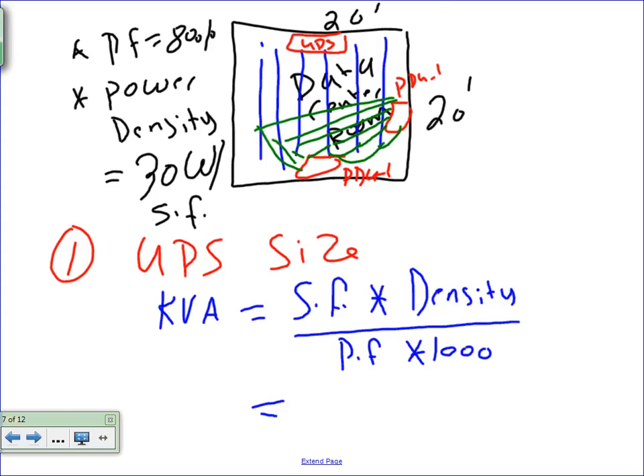Here are a couple of assumptions that you need to take. In order to size a UPS, we size it based on the computer load. The computer load is a function of the computer room. I decided for this to have a 20 by 20 computer room. I have my UPS and my PDU in it. These are all my servers. Data center power. The assumption is 80% power factor. Power density for this data center is nothing, it's 30 watts per square foot, nothing.